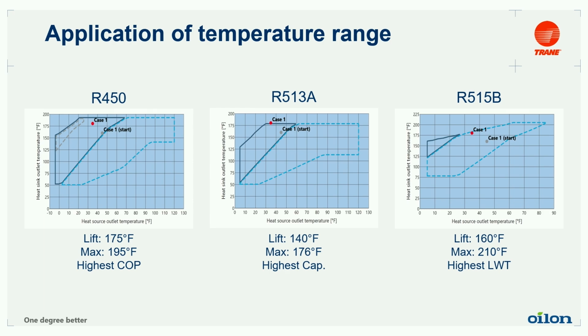Here is the same exact piece of equipment with three different gases in it. R450, we can do 175 degrees of lift and about 200 degrees leaving water temperature, optimized towards the highest COP. If we switch to 513A, we max out our capacity but suffer on leaving water temp and the lift. Or if we go 515B, we're able to get over 200 degree leaving water temperature. Those are some of the things we're doing, and it's not just with Oilon—we're doing that with our traditional products as well, playing with different gases.